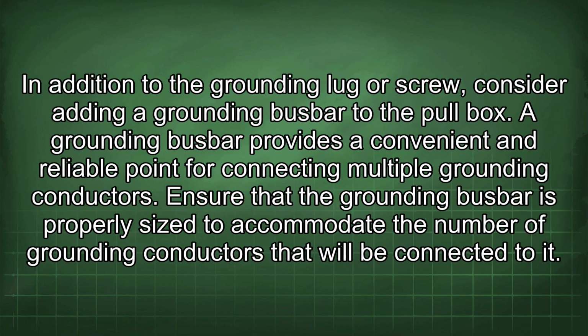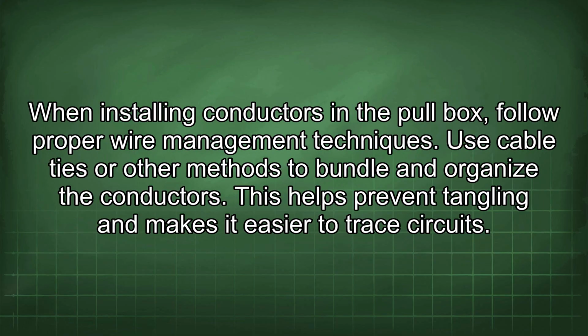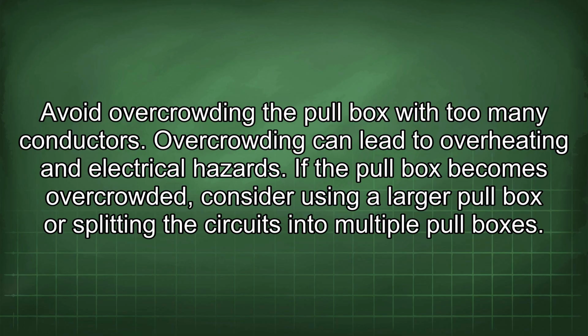In addition to the grounding lug or screw, consider adding a grounding busbar to the pull box. A grounding busbar provides a convenient and reliable point for connecting multiple grounding conductors. Ensure that the grounding busbar is properly sized to accommodate the number of grounding conductors that will be connected to it. When installing conductors in the pull box, follow proper wire management techniques. Use cable ties or other methods to bundle and organize the conductors. This helps prevent tangling and makes it easier to trace circuits. Avoid overcrowding the pull box with too many conductors. Overcrowding can lead to overheating and electrical hazards. If the pull box becomes overcrowded, consider using a larger pull box or splitting the circuits into multiple pull boxes.